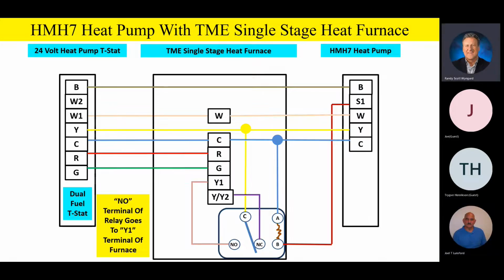Joel, I just want to make sure that the guys have a good grasp of this. You're talking about the relay going, one side of the relay going to Y1, Y2 for high blower speed, and going to Y1 for low blower speed. That is correct. Even though it's a single stage furnace.